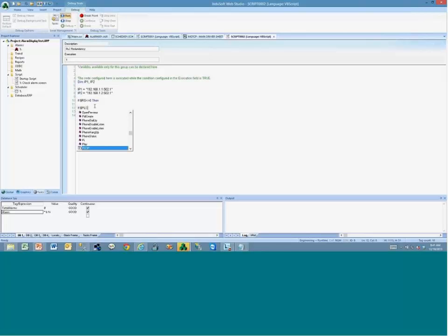So you can check if the PLC IP is equal to IP1, then the PLC IP should be swapped to IP2. Otherwise, the PLC IP is IP1. And here, for protection, for the first scan, you can say if PLC IP is equal to nothing, then PLC IP is equal to IP1, to have one to start with. So pretty much this will do the trick. Instead of running the script all the time, you can time it in the scheduler and execute it once every minute, or once every 5 seconds, for example. So after you swap, you give some time for the driver to connect and update the read status.